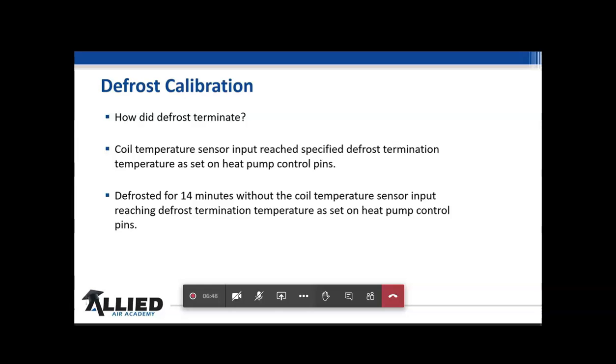Now, when we calibrate this, some of the factors that it's going to weigh in is how did defrost terminate? What had to happen for this board and the sensor to say the coil's clear? Well, that's always been a question that I get, and that's why I did it this way today. So the coil temperature sensor reaches the specified defrost termination temperature as set on the heat pump control pins. I'm going to show you those control pins, but I'm also going to show you the A3, and I'll get into that, but it has to reach that temperature.